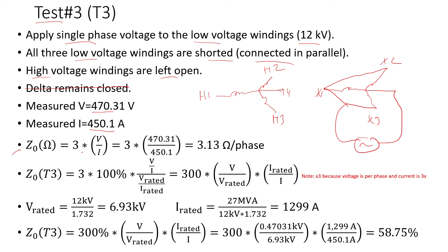Here is the equation to calculate the zero sequence impedance in ohms obtained from this test: three times the voltage divided by the current. That gives 3.13 ohms per phase. I multiply by three because the measured voltage is line-to-neutral — it's a per-phase voltage.